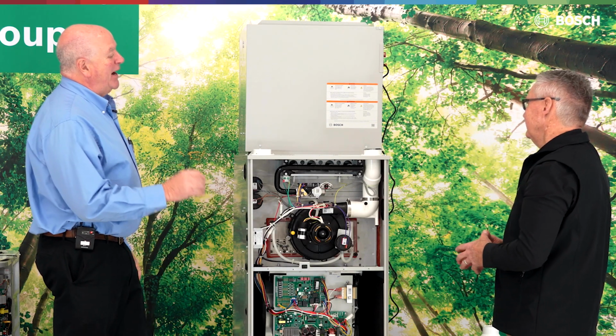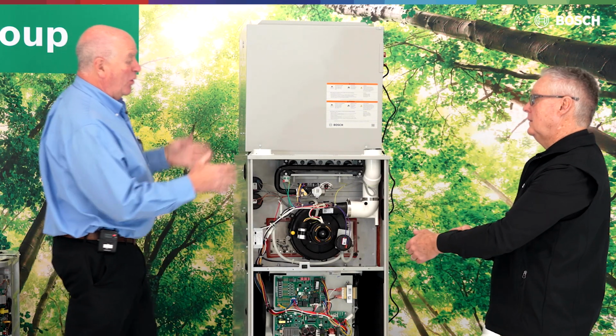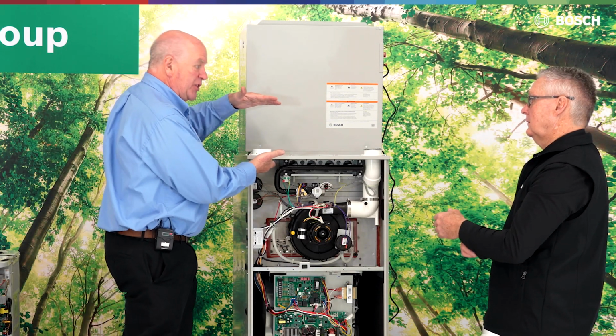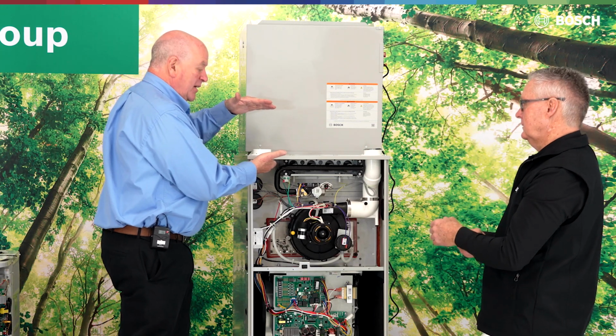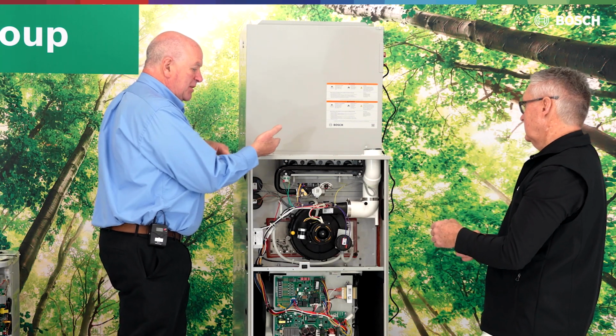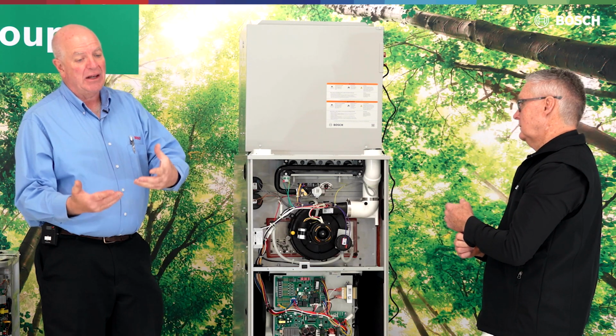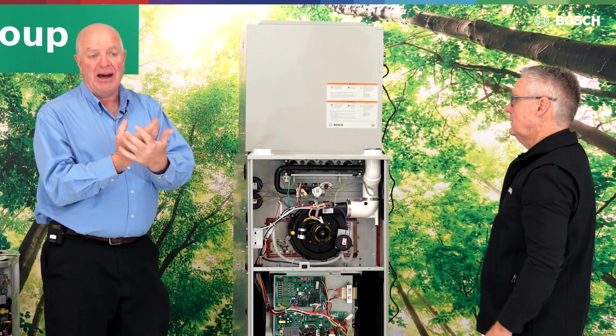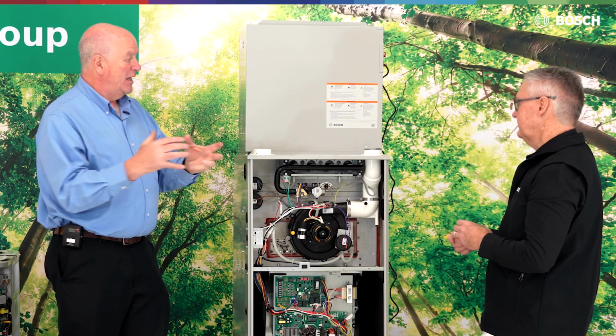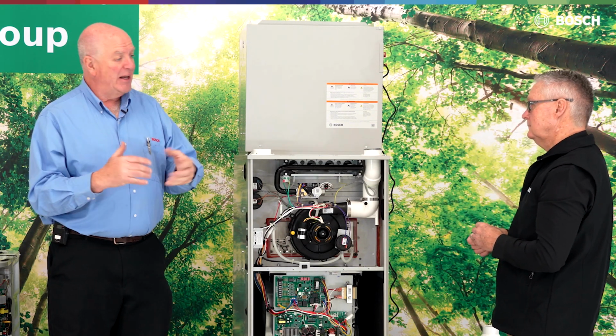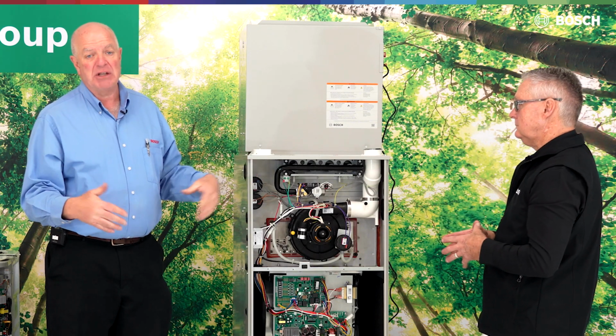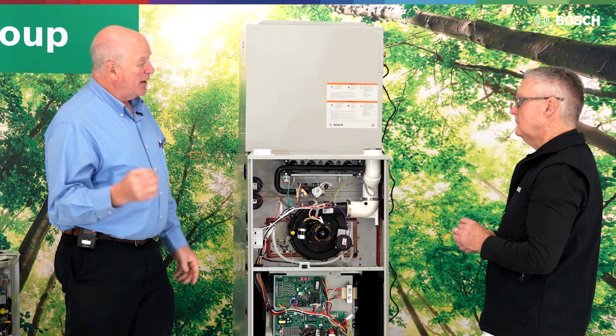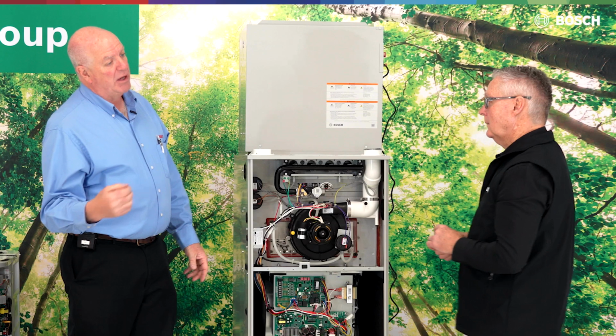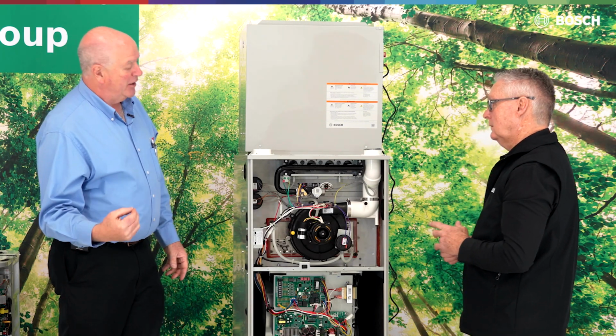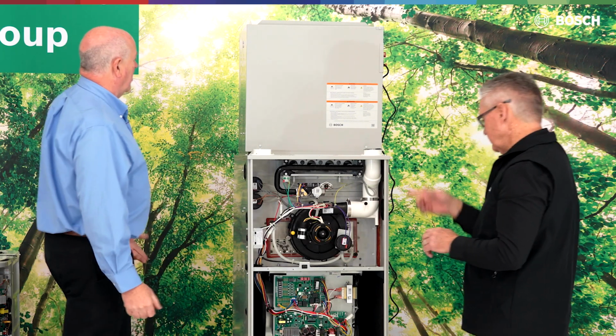So we're going to recommend an aftermarket condensate pan on oil furnaces with a 6-inch elevation above the heat exchanger. If we're not at 6 inches, there's a chance, and it's probably never going to happen when the unit's running, but if there's a power outage, that residual heat would stay. It'll melt. Is our pan anything different than anybody else's? No, they're all plastic. We just bring it to their attention. So we're trying to bring out all the fine points, what you can expect if there'll be a problem.